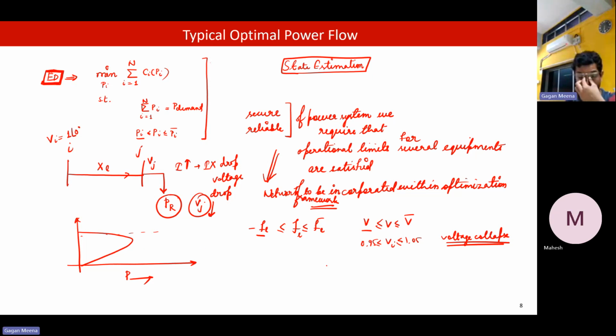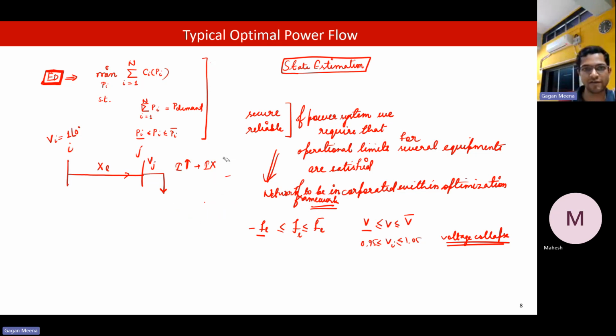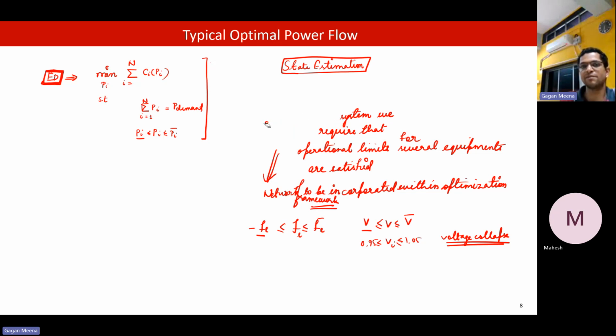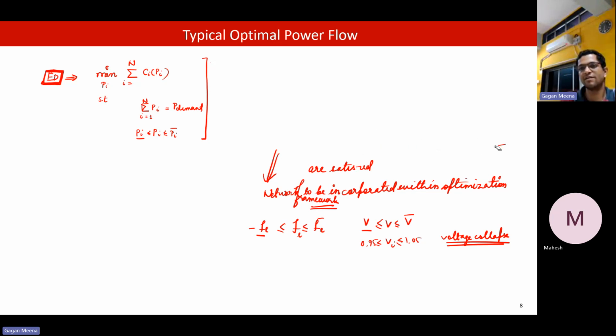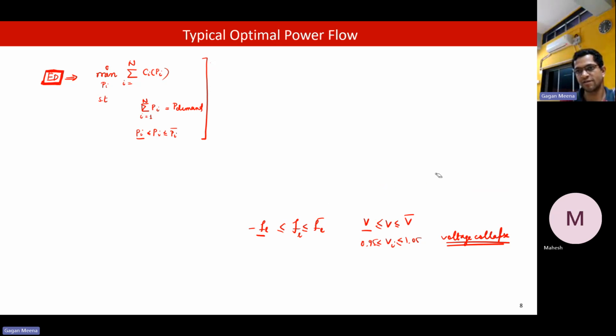That's why we want the voltage at each bus to be within this minimum-maximum band of 5%, between 0.95 and 1.05 per unit. Several other limits exist, like the reactive power sources we have seen. We have on-load tap changing transformers, and they have a limited number of taps. So if we have a variable for tap, it should also be within its operating range. If there are 16 taps, then the variable corresponding to the tap of the transformer cannot go beyond 16. And it is also a discrete value.